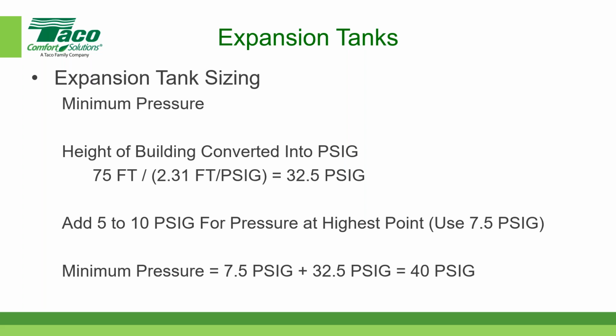Some people will actually design the piping system in such a way that they can open a series of valves so the expansion tank, the bladder, is open to the atmosphere, which is effectively like having it not connected to the system. But you have to have a series of valves in the right location. We purposely did not show that this evening because everybody has a different method of connecting it to the system for service and for pre-charge and all that other type of thing. But the simplest way to think of it is that you pre-charge the air side before you connect the expansion tank to the piping system.